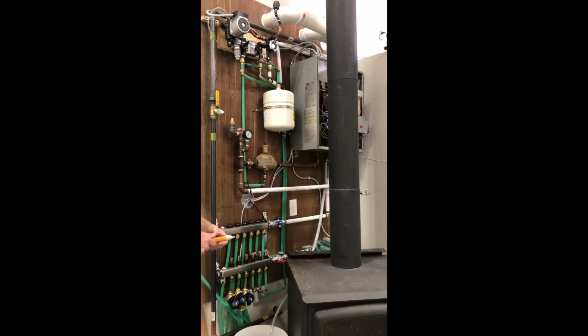I'm going to need to add another heat exchanger up there with 3/4 loops on both sides, because I'm just not getting enough flow through to keep the heater happy. It's cutting in and out, trying not to boil over. So we're going to have to add another heat exchanger to add to the capacity there.